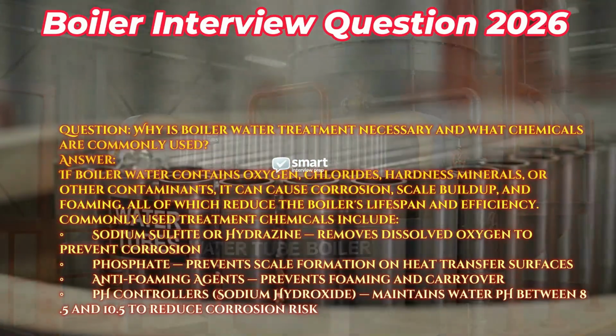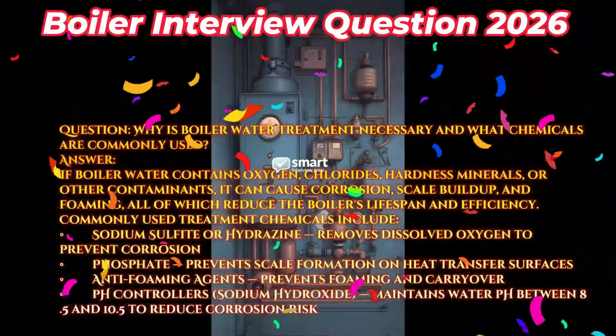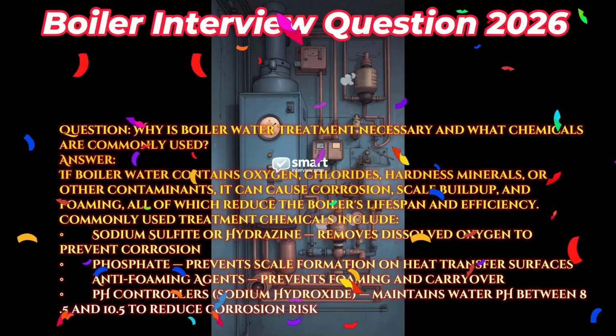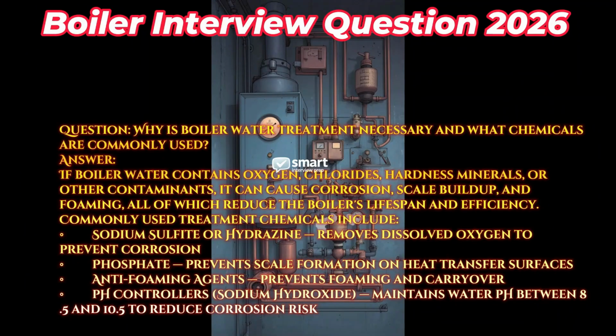Anti-foaming agents prevent foaming and carryover. pH controllers, such as sodium hydroxide, maintain water pH between 8.5 and 10.5 to reduce corrosion risk.